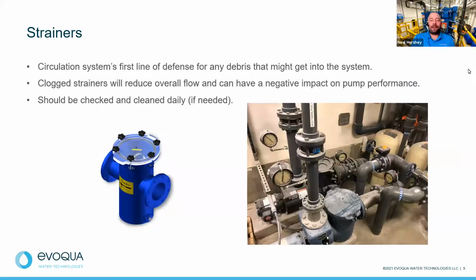So strainers are important to check. I recommend checking them daily. You never know, especially in an outdoor facility, what's going to come through your system, and if you're not keeping track of that, it's going to have a major impact on your circulation system. If that strainer basket gets clogged up, the overall flow rate's going to drop. Your pump's going to potentially start to have some issues, especially if it's an ongoing thing. It's a pretty simple maintenance item.